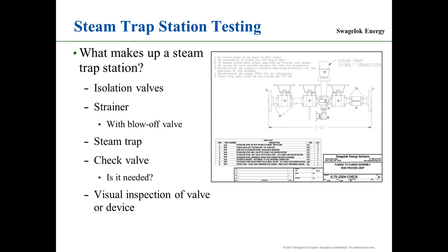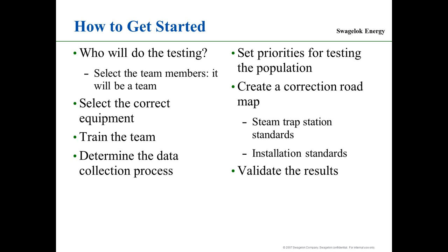The next component is a check valve. Is it needed? People always say, you put a steam trap in, you've got to put a check valve in behind it. Why? Who told you that? The person associated with steam with a check valve? We do use check valves in certain applications and in other applications, no, we do not use check valves, and not to get into that. So, and a visual inspection valve or device, and we'll talk a little bit about that.